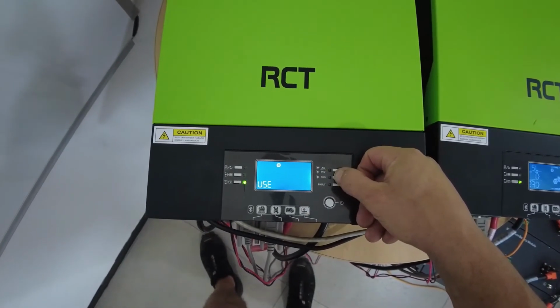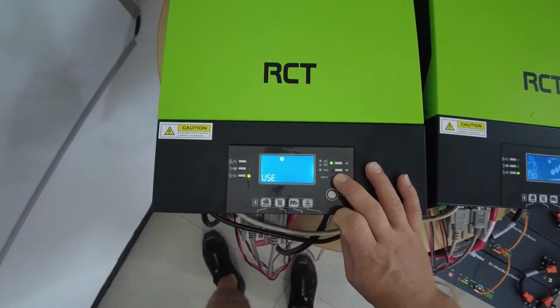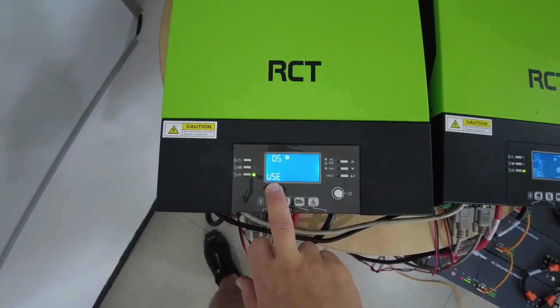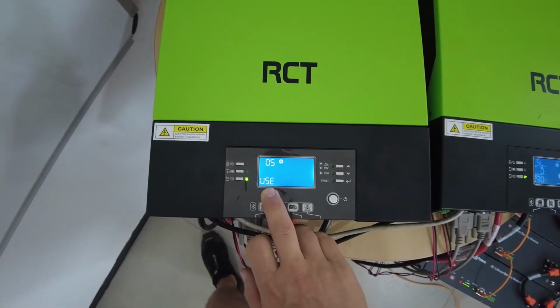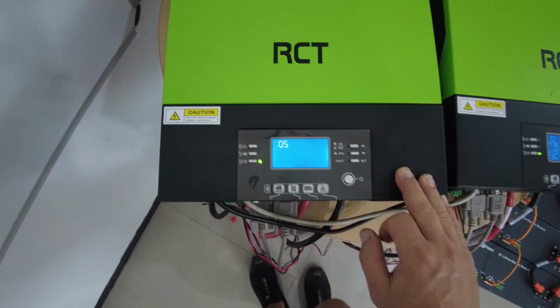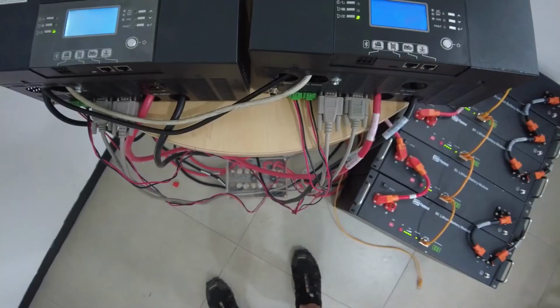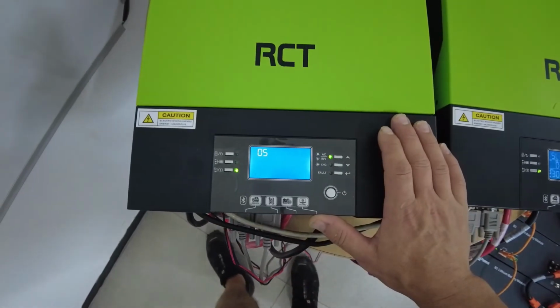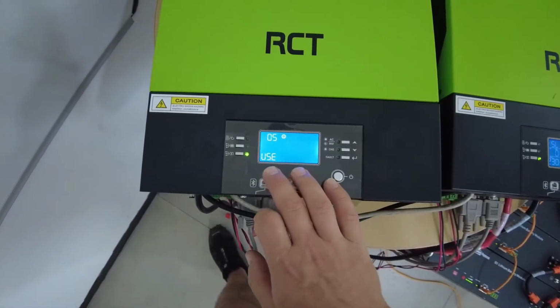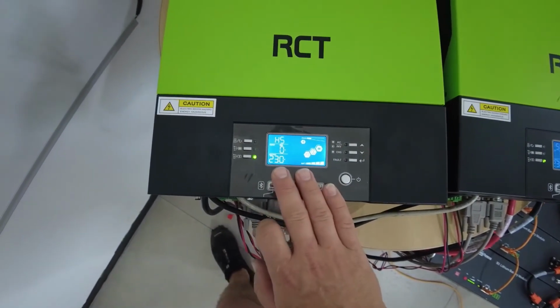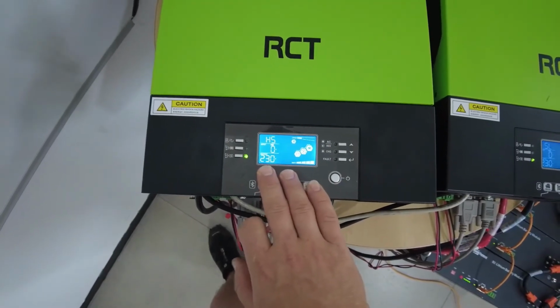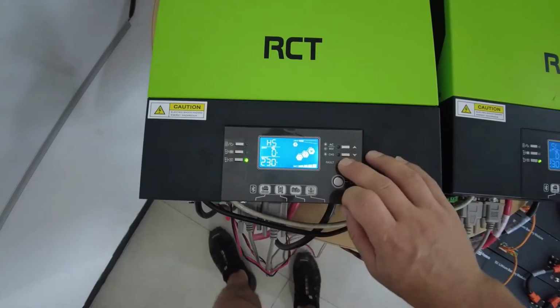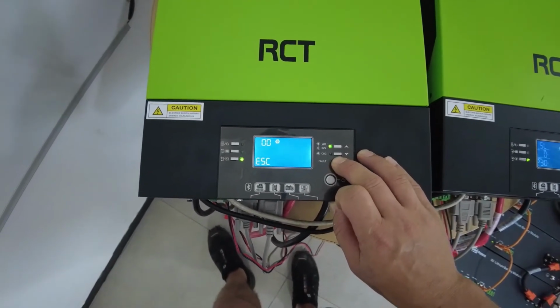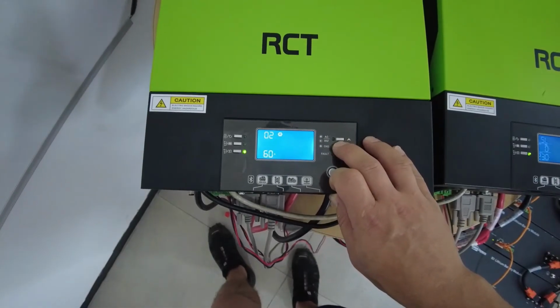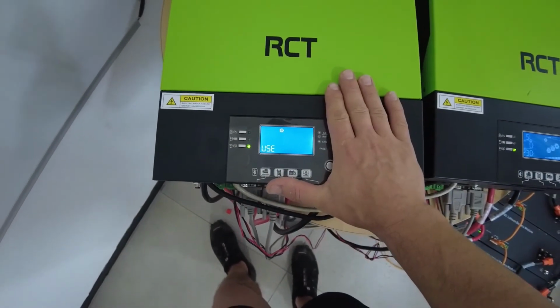Go down to your battery type setting number 5. Now this needs to be on USE. It should not be anything else. Now, because we have it connected in parallel, generally this setting will automatically change. But just for argument's sake, do not come and change this to PYL or LIC as well, because those are the two settings you need to set on the inverter that's going to communicate with the battery. As mentioned, we're not going to set this one up to communicate with the battery. It's going to be this one. So this needs to be on USE.